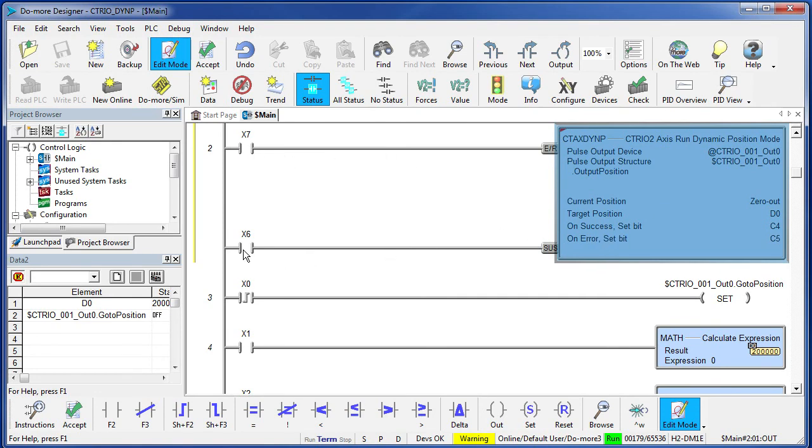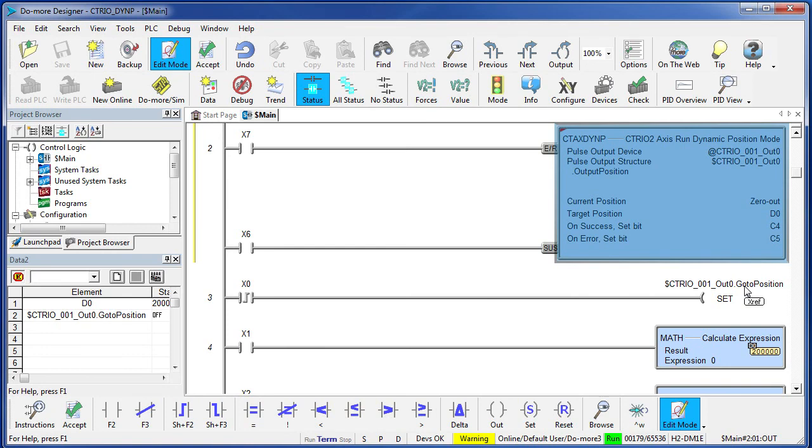We'll enable that instruction with X7 and we'll suspend it with X6. So, just like those notes in the instruction said, once we enable this instruction nothing happens. You actually have to set this go to position bit on our device to get things to move. We are going to use the rising edge of X0 to do that in our example.